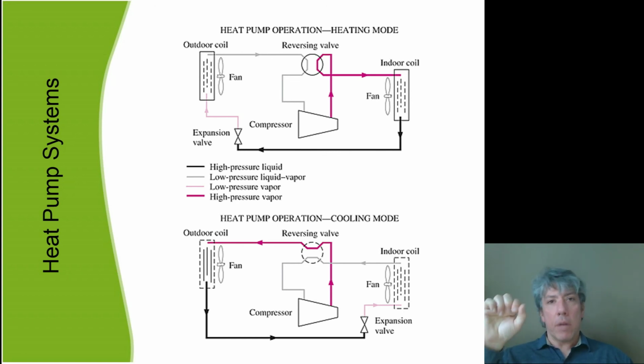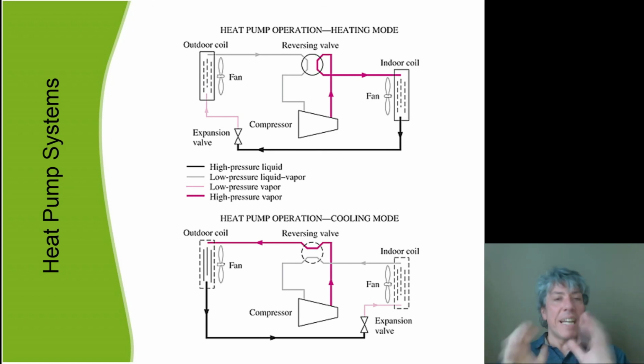So the refrigerant then has lost some energy, and of course the indoor coil, what it has to do now is prevent anything but liquid from leaving. It's interesting because in cooling mode, going back to the lower figure, the outdoor coil is called the condenser and the indoor coil is called the evaporator. But in heating mode, what's going on is the indoor coil is actually condensing. So the condensing coil is inside, the evaporating coil is now outside. And so it's a little bit confusing, in terms of terminology, because they've traded spaces, right?